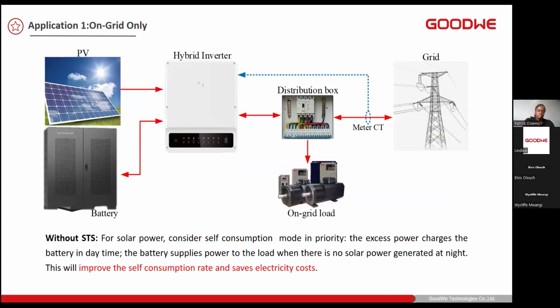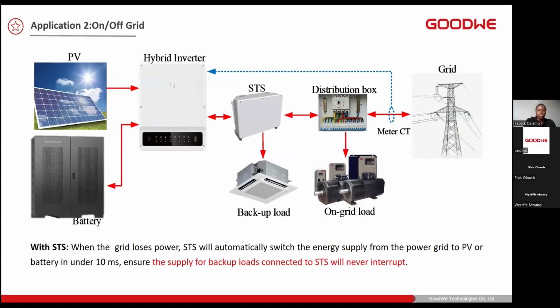This is an application scenario of how your system can work. Without the STS, which integrates the backup on the generator, your system will be restricted to grid-tied, or will only work with the grid. Okay, and yes, self-consumption with a grid-tie solution, but this can be made a better solution when you add the STS. Now with the STS, you can back up your whole plant or your whole community, as I mentioned before.